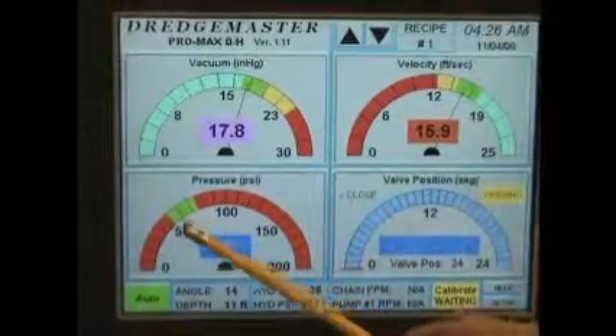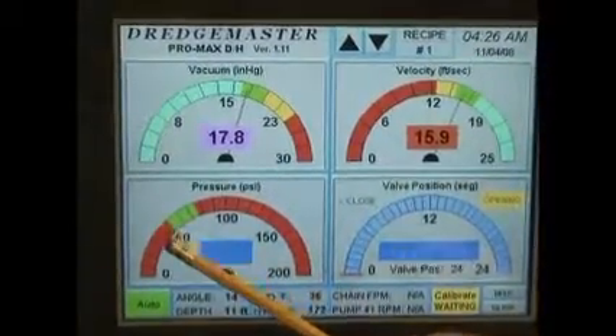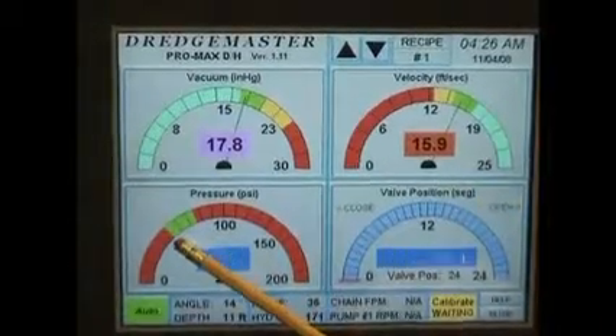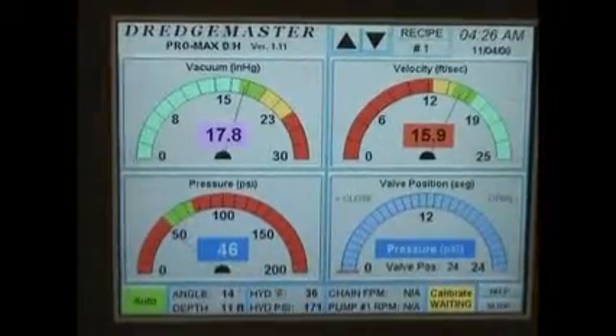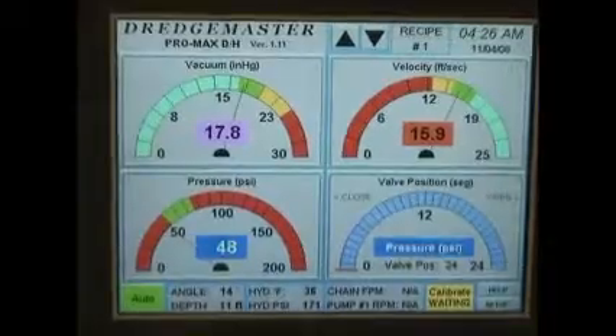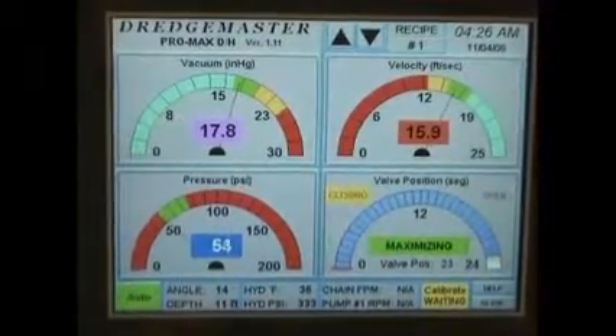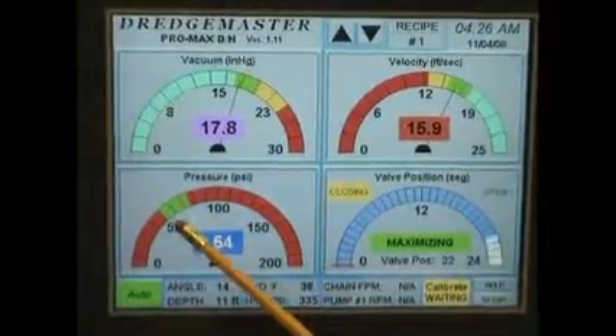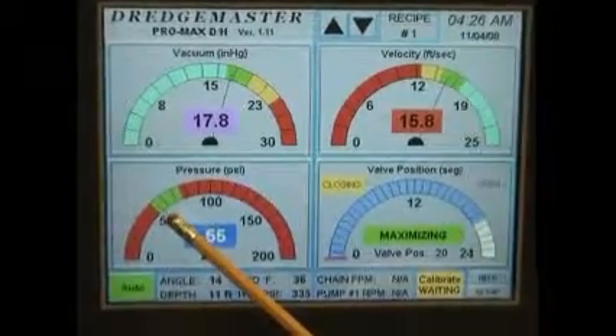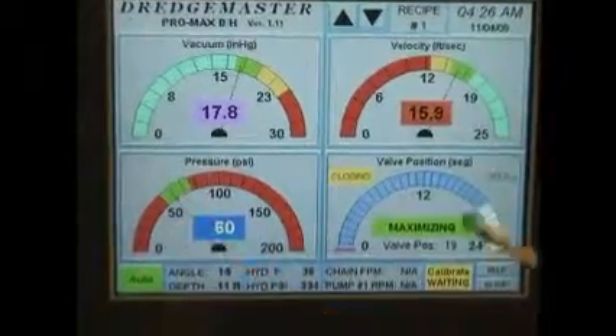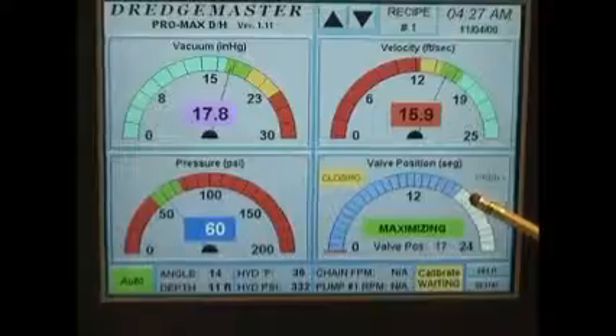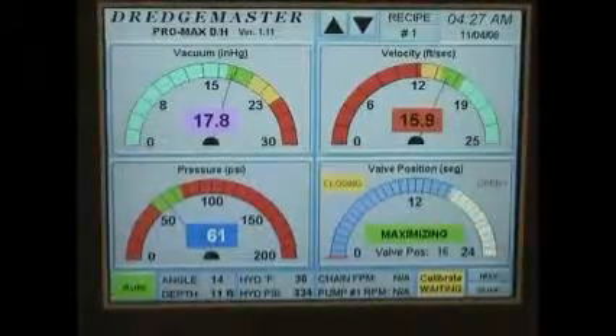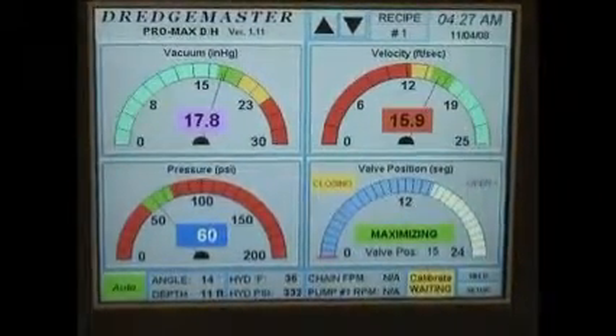So you want this set point between your green and your red area to be just before you start to cavitate a pump. So we eliminate that from happening. Once we got enough material back in the suction side, our pressure is going to come back up into a normal range. As soon as that happens, our valve can start closing itself back down.